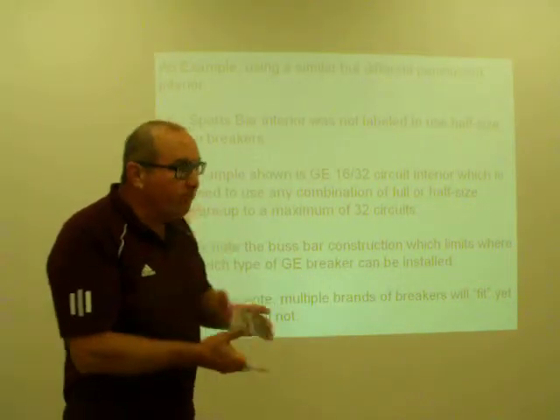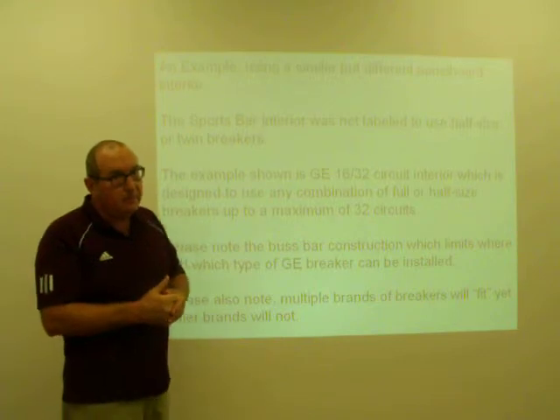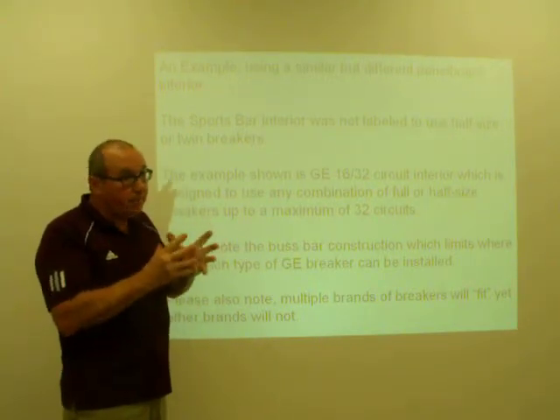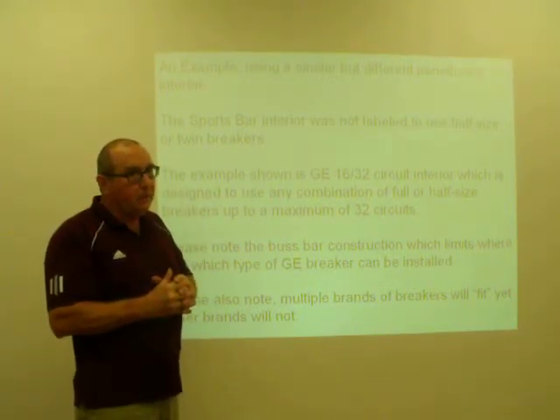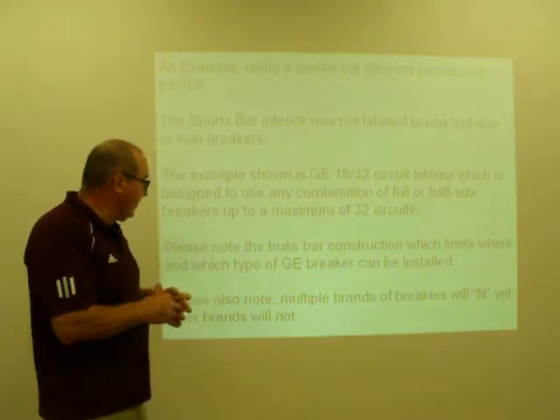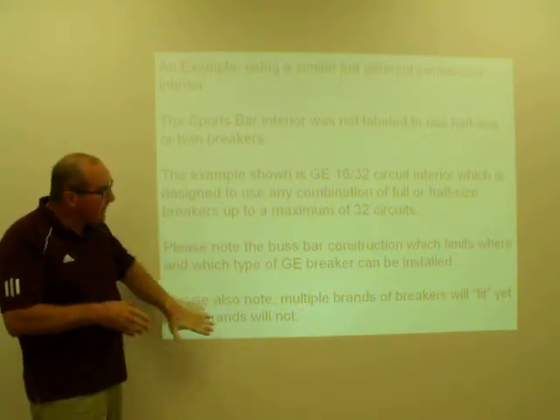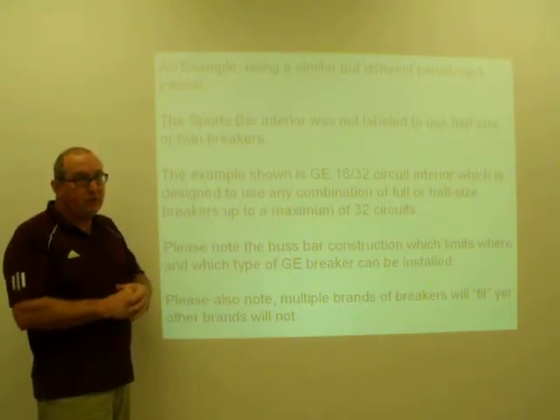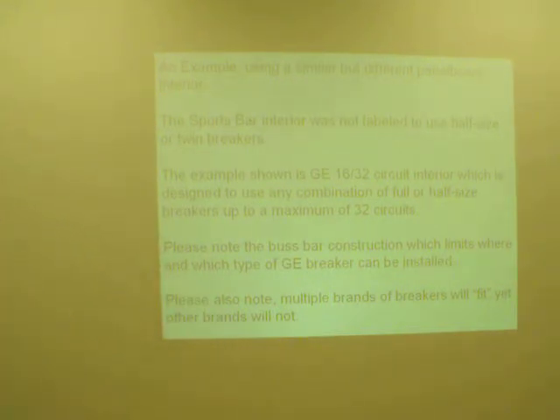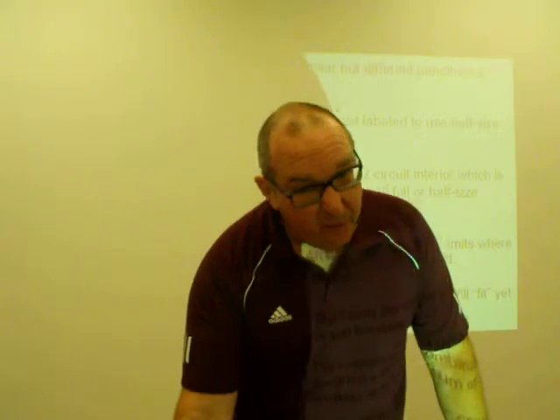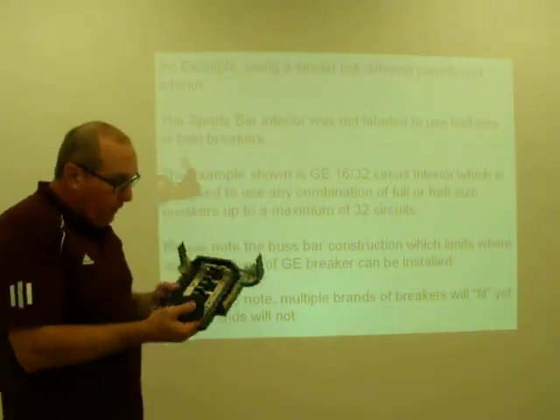So depending on the type of bus bar you have and the brand of panel, you may be limited on where you can physically place a breaker. Although there are ingenious people that come up with ways to get around that too. So the fact that a breaker will fit, you can physically plug it in, and I can demonstrate that to you even further with some of the breakers that I have brought with me here, that does not mean that it is safe or legal to install that breaker in that panel board.